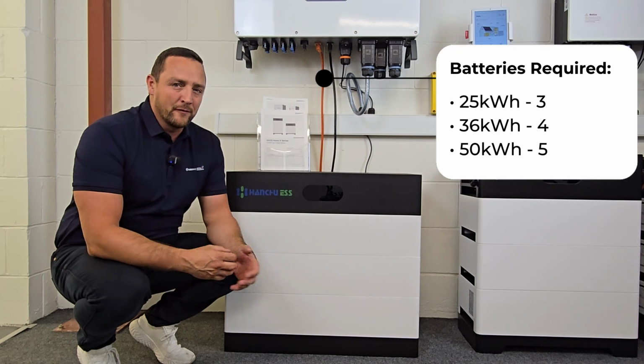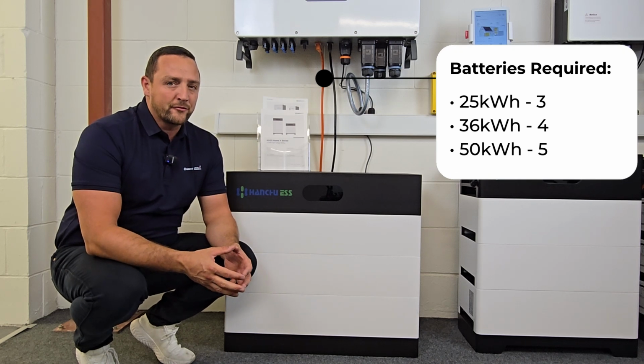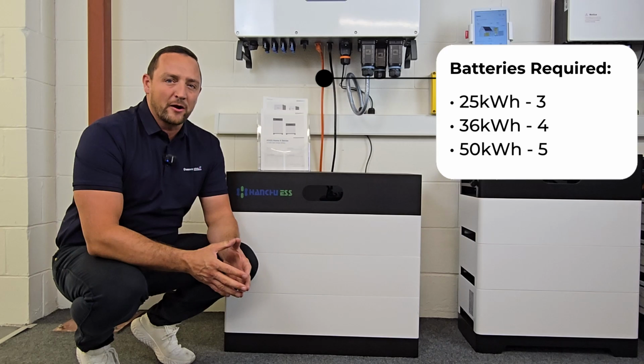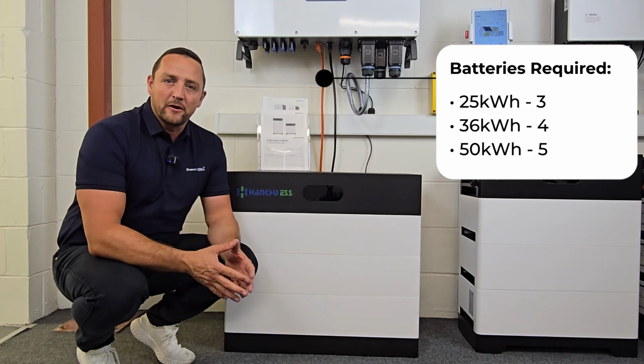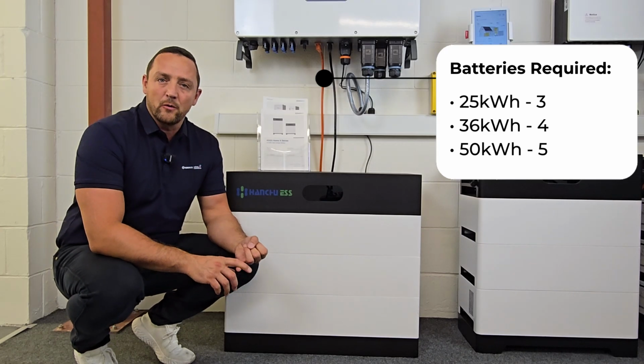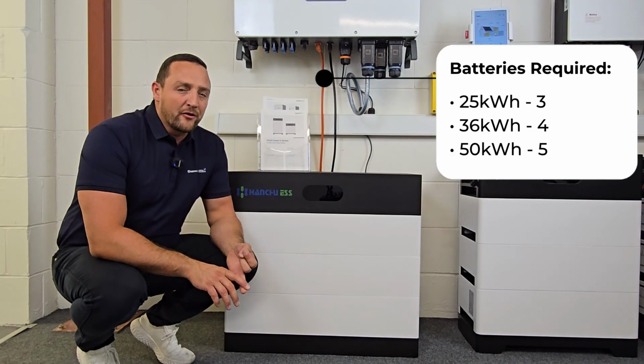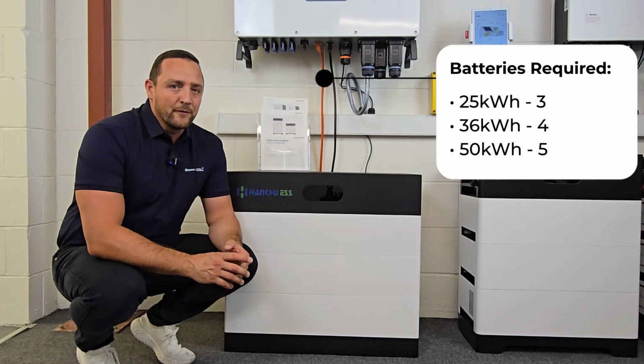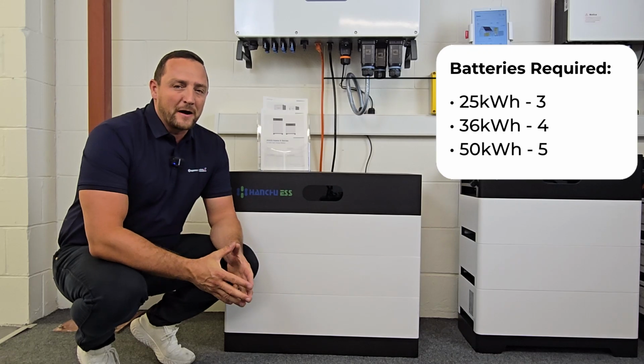Like I said earlier in the video, we do need a minimum number of batteries to achieve the maximum charge and discharge rate through each inverter. So let's just go over that again. With the 25 kilowatt, you would need 3. With the 36 kilowatt, you would need 4. And for the 50 kilowatt unit, you would need 5 batteries.